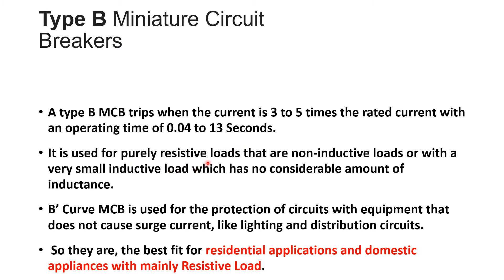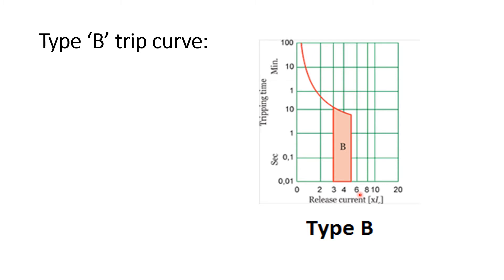It is used purely for a purely resistive loads that are non-inductive loads or with a very small inductive load which has no considerable amount of inductance. So it is very clear that B curve MCB is used for the protection of circuits with equipment that does not cause surge current like lighting and distribution circuits. So it is best fit for residential applications and domestic appliances with mainly resistive loads. So whenever you want to install any MCB for your residential purpose in that case you have to go for type B type MCB.